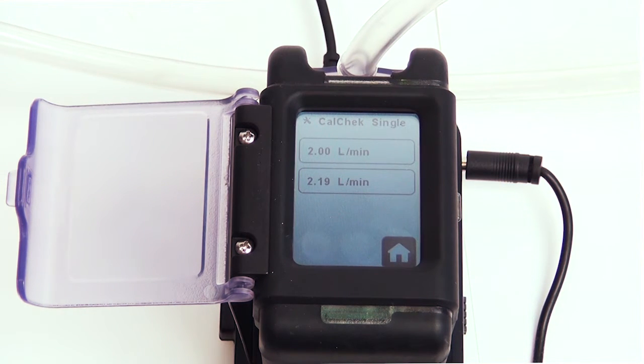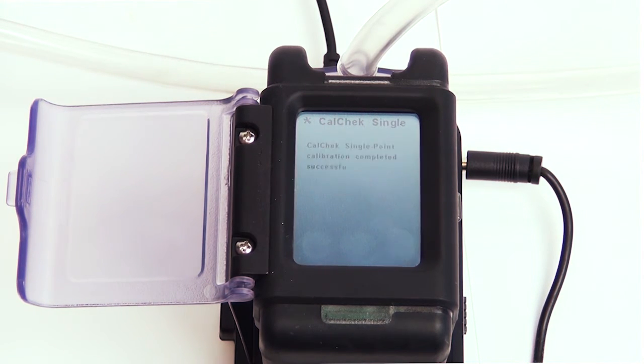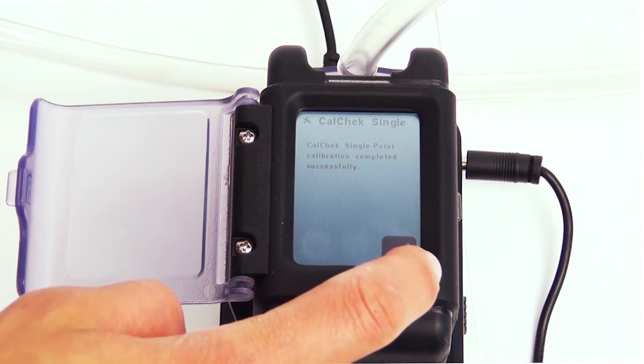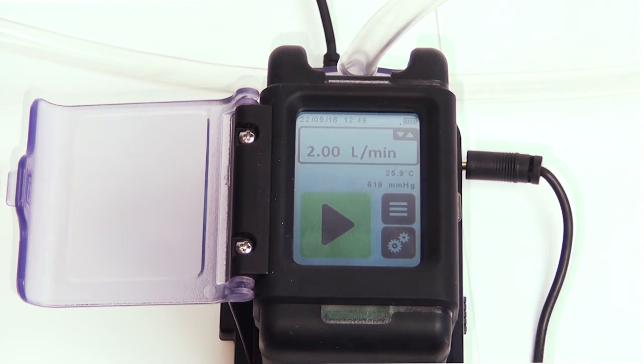The pump will calibrate automatically and will display the set flow rate on the top box in the screen, and the bottom box will show the flow rate reading from the Defender in real time. At any time, pressing the Home button will cancel your calibration. If the calibration is successful, the CalChek Single screen will read, CalChek Single Point Calibration completed successfully. To accept, touch the check mark and you will be returned to the home screen.